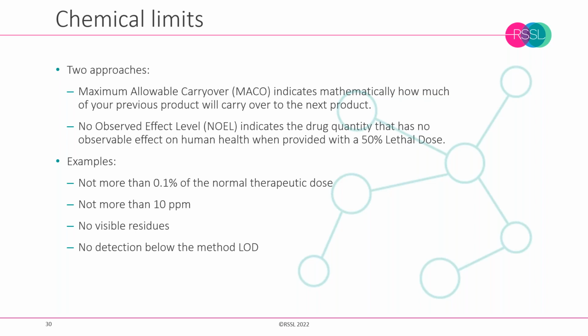And there are different criteria that spring from that. So one set of criteria is to have not more than 0.1% of the normal therapeutic dose of any product appearing. Another is to have not more than 10 parts per million of any product appearing likely to cross-contaminate another product.